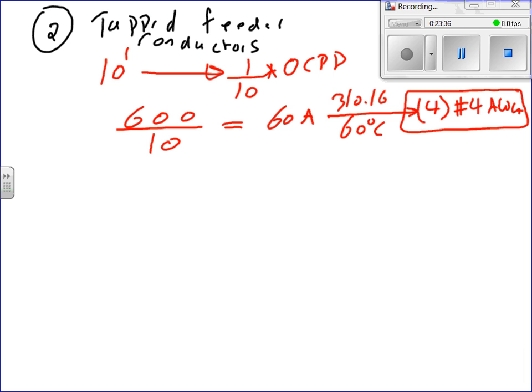I have a question. Yes, sir. The 10-foot feeder tap says tap conductors must have a capacity not less than 10% of the overcurrent protection device. So yes, they could be higher. I can tap 500 kcmil from this feeder. Bring it on. The key point: this is the minimum, guys. I can't emphasize that enough.